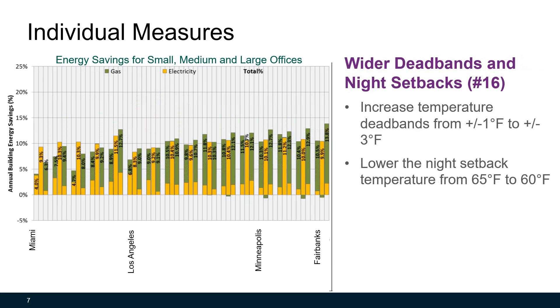Wider dead band and night setbacks is another advanced control strategy you can implement. Increasing the temperature dead band from one degree to three degrees and lowering the night setback temperature from 65 to 60 will save roughly 10 percent of natural gas or electricity.